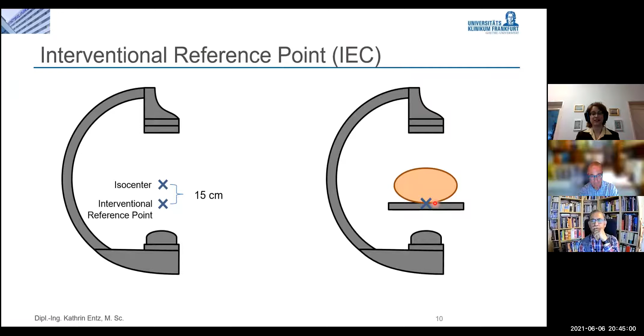Of course, this is only for standard parameters and a standard patient. If you have anything deviating from that, then the interventional reference point is not as accurate a description for the peak skin dose. For example, if you put the table or the patient higher and move it closer to the detector and further away from your tube, which is actually supposed to be good because you're lowering the dose for your patient, then the interventional reference point happens to be outside the body and not on the skin. So you're overestimating the dose in this case.